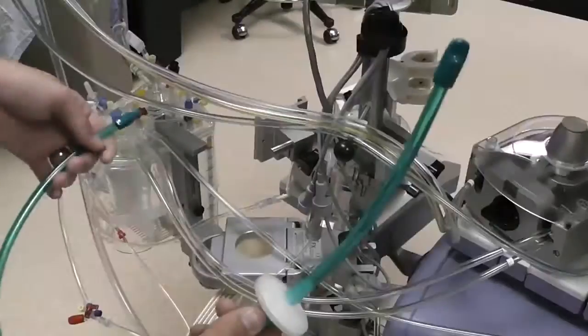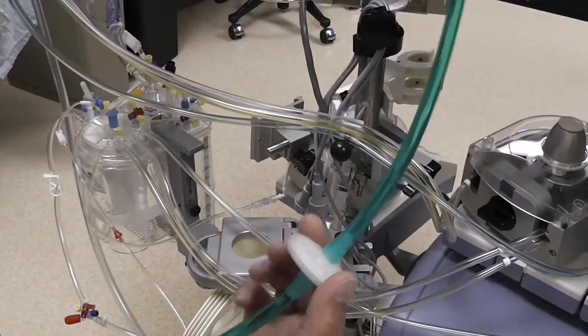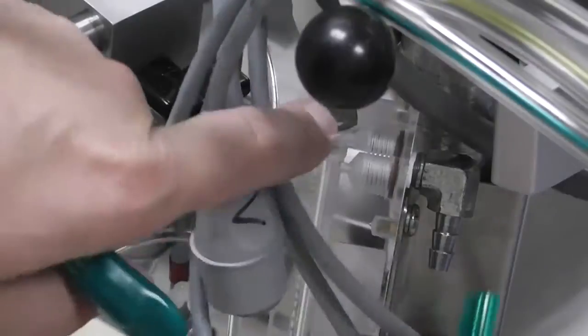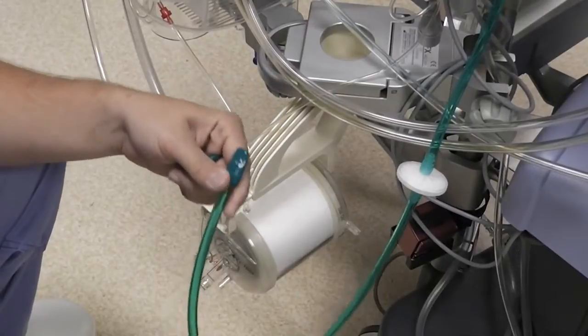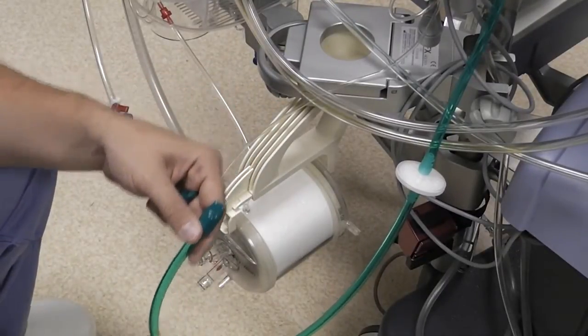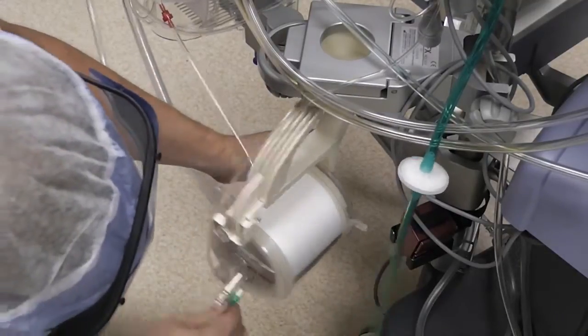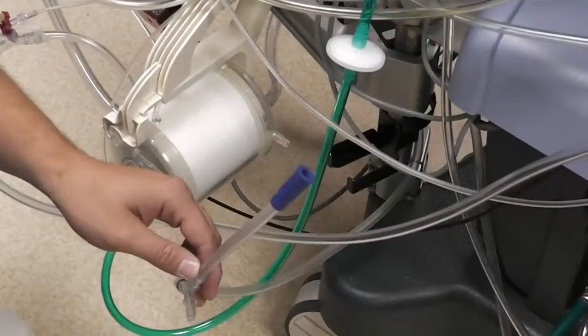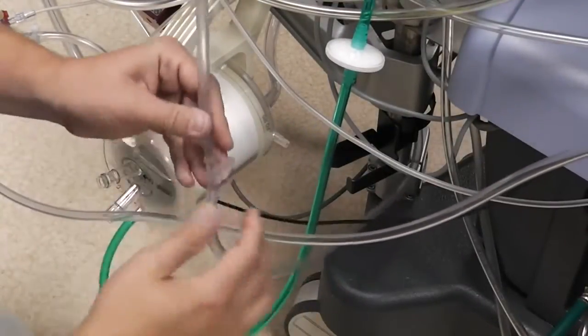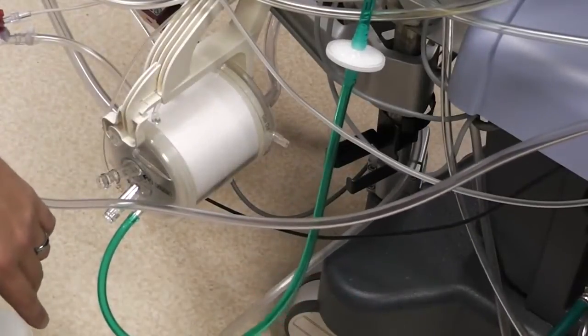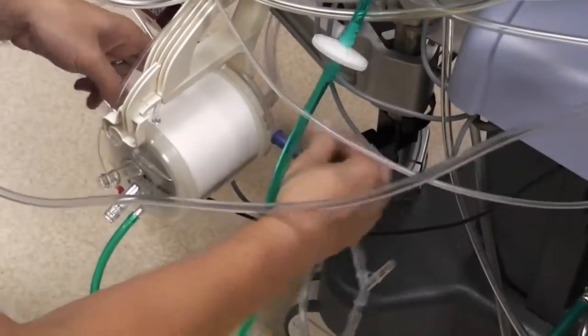Okay, we're going to take our gas line and we're going to put the filter side up, and we're going to attach that to this barbed connector back here. Slide that all the way on. And the other side of this gas line is going to go on to the oxygenator below the water lines. The gas inlet is down here. After we've attached our gas line, we're going to attach our scavenge line, which is usually tucked up under the pump here, and we're just going to attach that to this back port on the oxygenator.